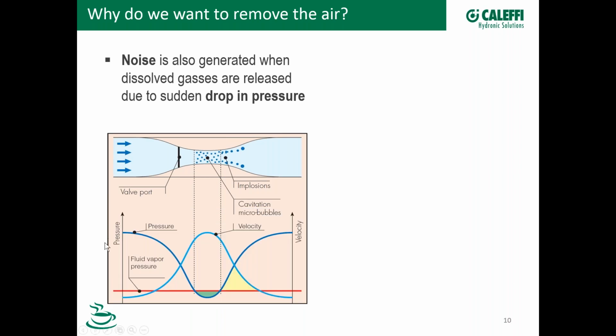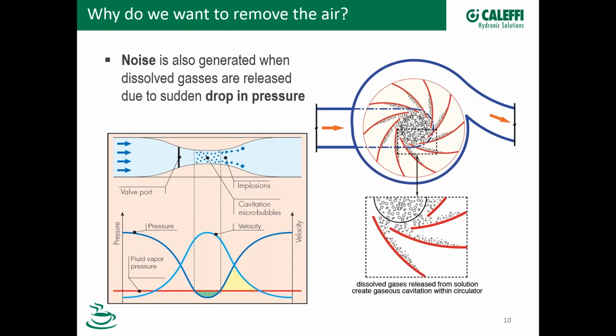And that looks like this on a graph. So let's look at this light blue line. Here's our velocity as we come through. The velocity increases and then peaks right here at the smallest cross-sectional area, and then it drops again as we exit. So here's the inverse proportion, the pressure. This diagram shows the pressure going below the vapor pressure of that fluid, and that's why these bubbles form right here. The same thing can happen in the inlet side of a circulator. Those dissolved gases can again be released from the solution and create cavitation right in this area of a circulator because of the velocity and the low pressure.